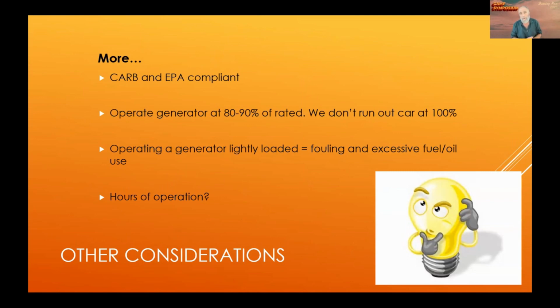Also, generators don't like to be lightly loaded. You want to keep a load on them. Otherwise, you'll have fouling, you'll have fuel and oil burning unnecessarily. And also with diesel generators, you have something called wet stacking, which can create a fire. Hours of operation is another consideration. Are you going to run it for a few hours a day, or are you going to run it 24 hours? That will dictate what kind of generator you end up with.